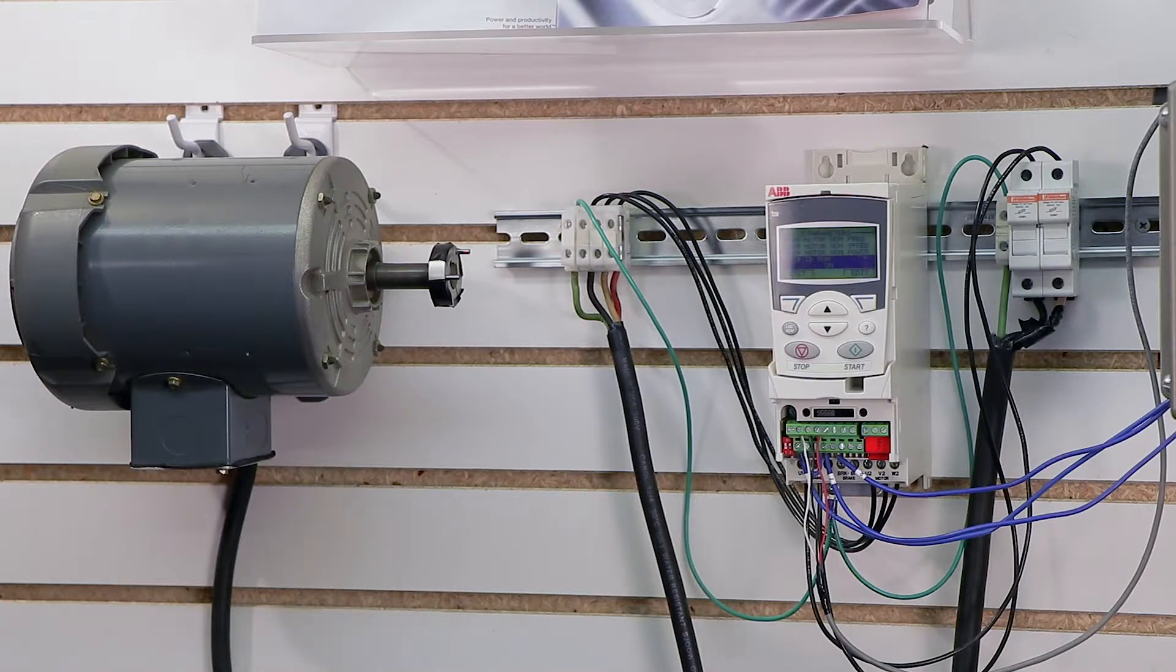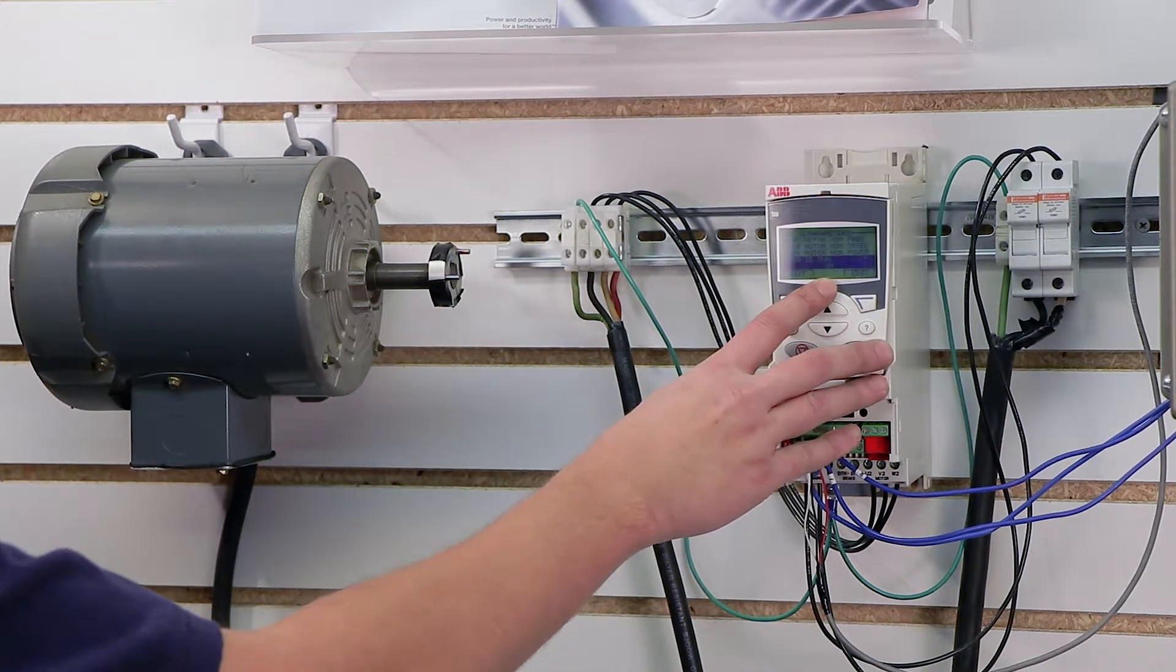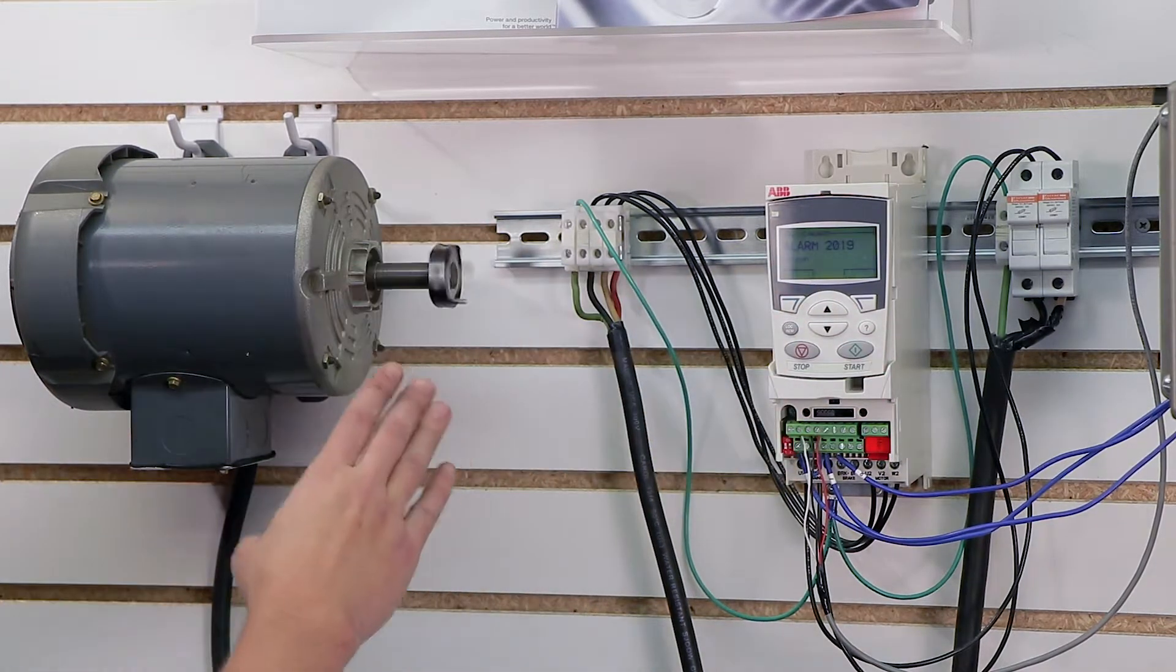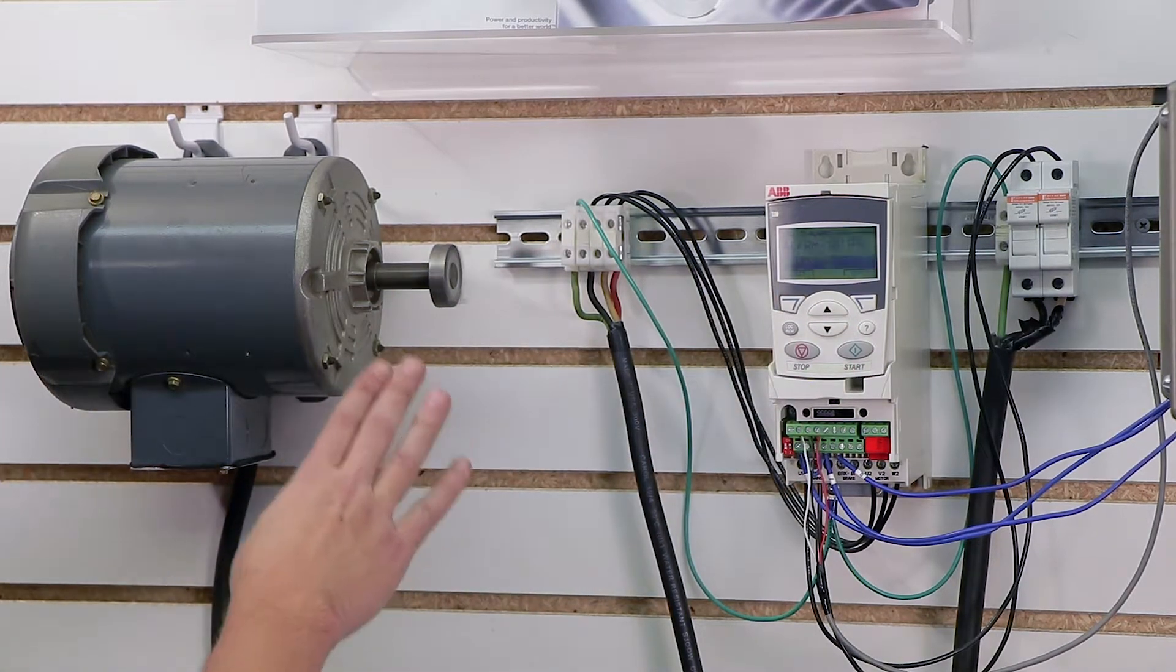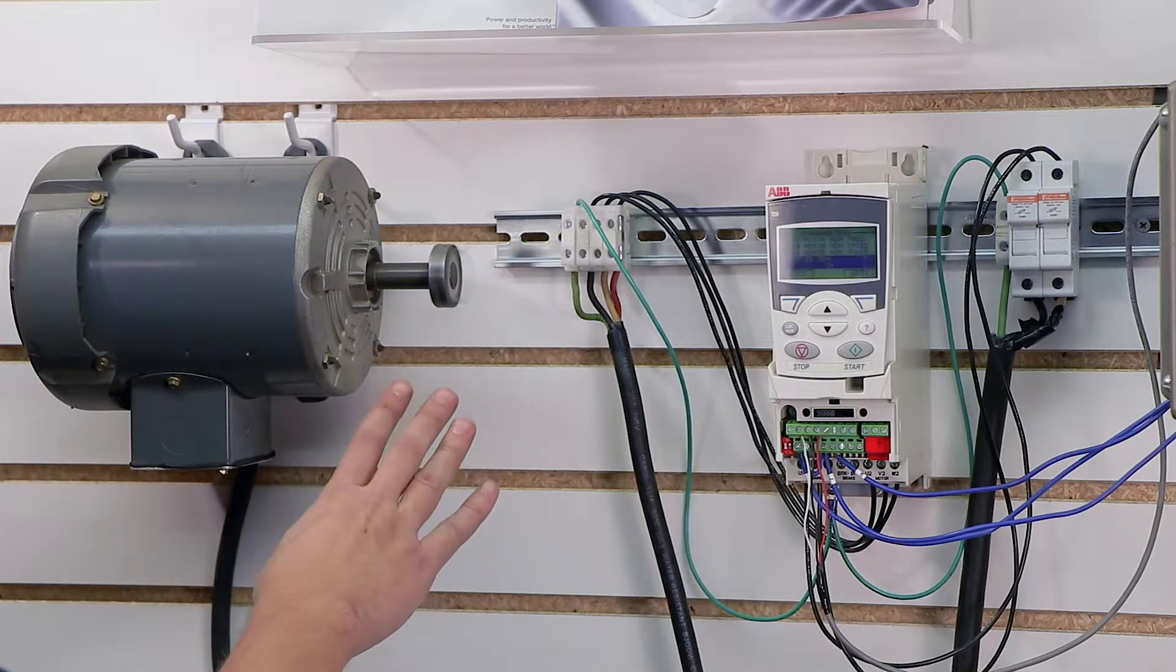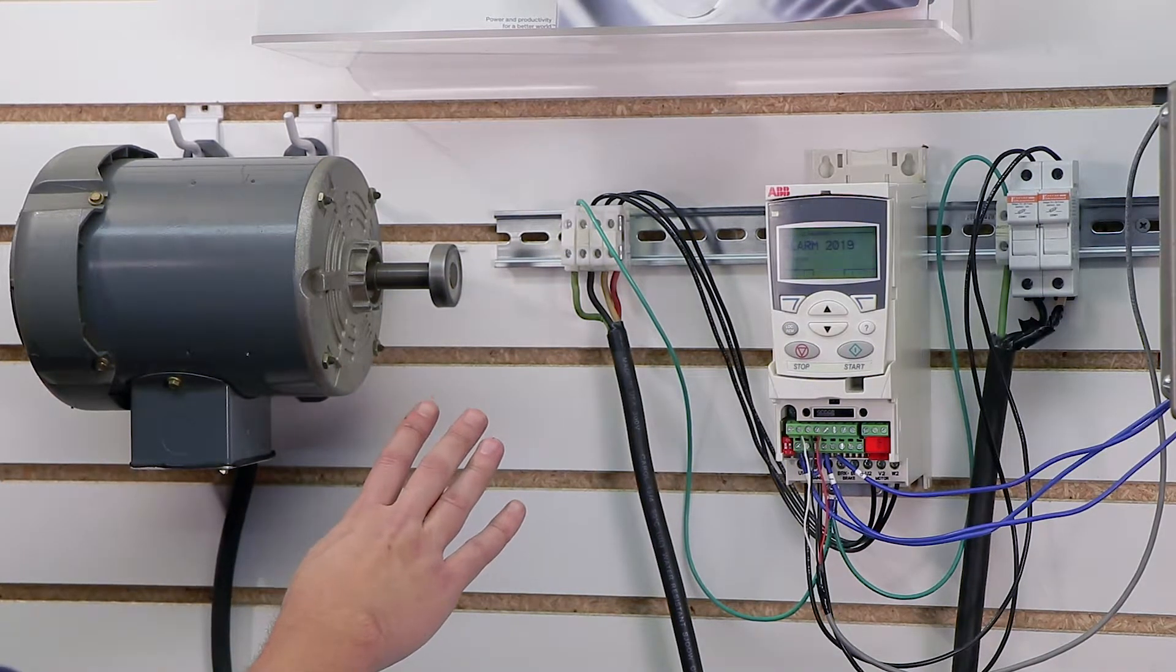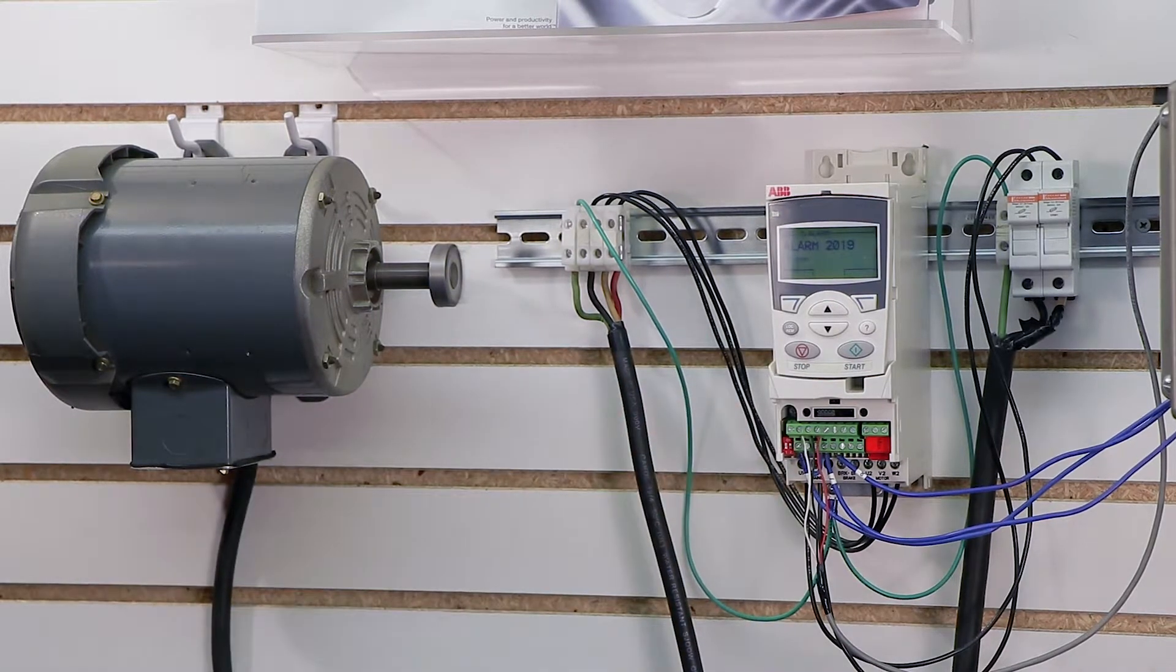And it's running it now. You'll notice it's whining a little bit. One important note to make is while it runs the ID run, it is going to rotate the motor, so before you run the ID run, make sure you disconnect the motor from any load and also make sure your direction of rotation isn't going to cause any damage to any external equipment. So right now it's running the ID run, which can take up to 60 seconds.